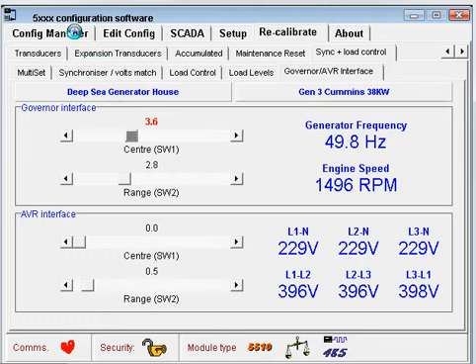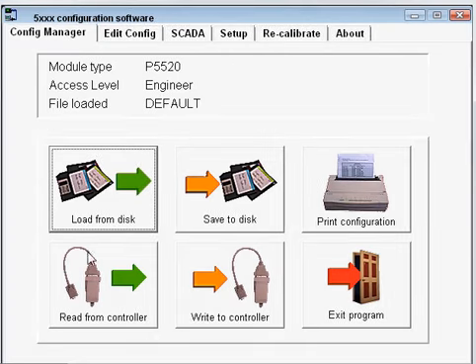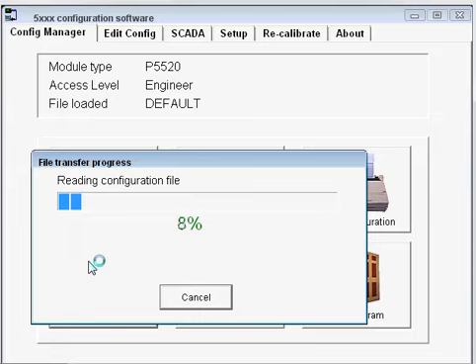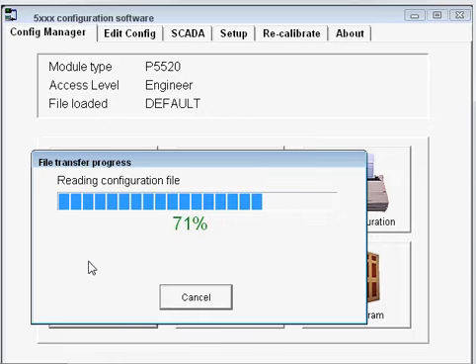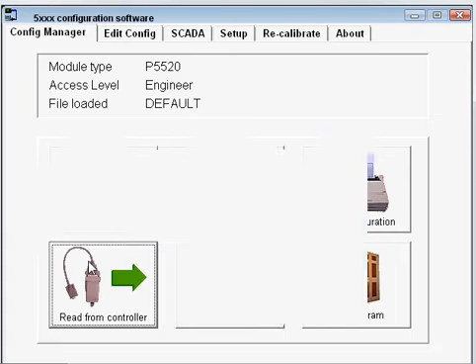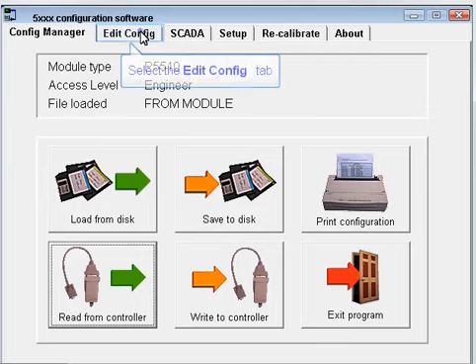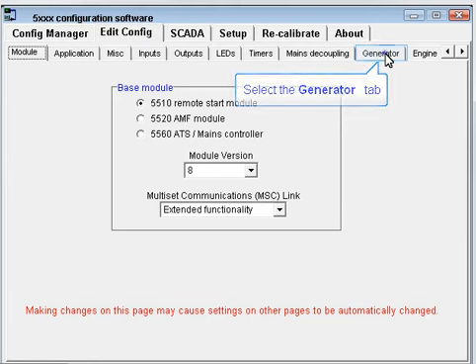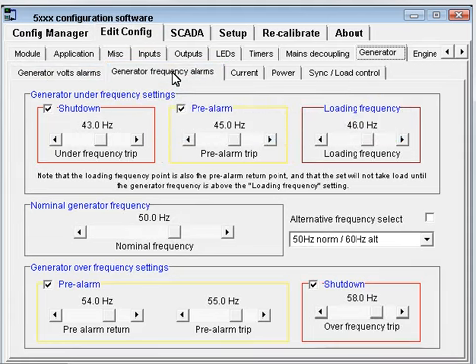We've just checked that we have control over the speed. We now need to check the range of this control. Read the configuration from the controller, then navigate to the generator frequency settings page as shown. Change the nominal frequency of the system — increase it by 2.5 Hz.